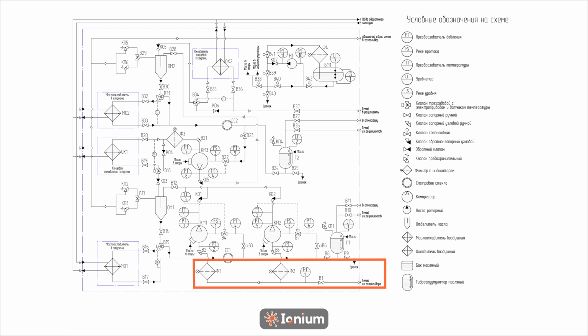Let's explore the technological process behind the operation of the compression unit. Helium is dispensed at a rate of 1 kg per second or 21,630 normal cubic meters per hour from pressurized gas holders, maintaining a pressure not exceeding 1.05 bar and a temperature of about 26 degrees Celsius, close to ambient conditions, and then passes through the mechanical cleaning filters marked F1 and F2, then is drawn into two identical screw-type, oil-filled compressors of the first compression stage, designated KM1 and KM2, where the geometric volume changes between the drive and driven screws, compacting it along their rotational axis to an absolute pressure of 5.3 bar.